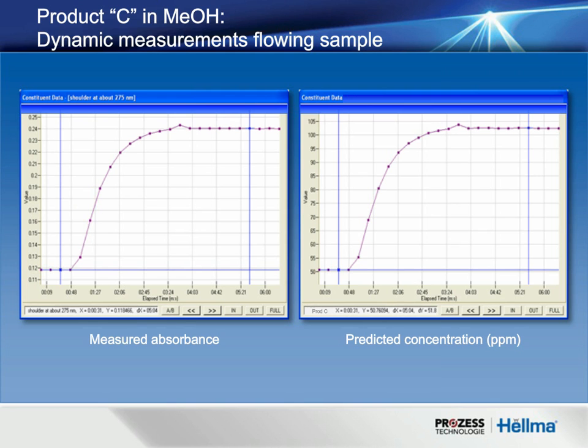So in this case, you can see that in this plot on the right, as you start rinsing your vessel, you start seeing that the solvent starts picking up the API, and eventually after a few minutes, it's saturated with the API around a little over 100 ppm, and so further rinsing of this product really doesn't accomplish anything. So with this indicator, this would also just be a valuable real-time feedback, so that now the vessel can be purged and rinsed with clean solvent until we would see the opposite curve of this, where it's finally the elimination of this product, whether that's down to a 1/1000th or to a ppm standard.